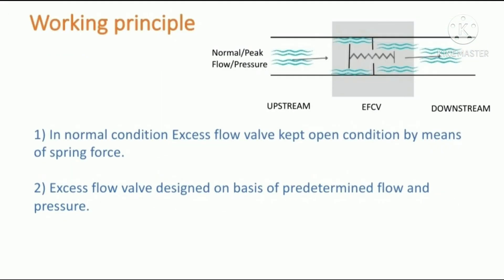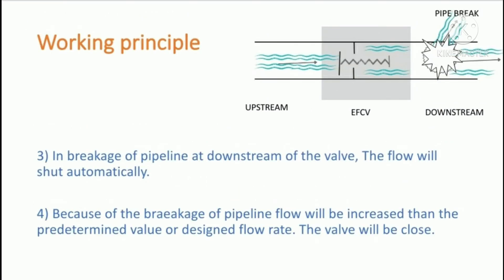Working principle: you can see the sketch of the excess flow valve showing upstream, downstream, and the flow of the fluid. In normal conditions, the valve is kept open by means of spring force. The excess flow valve is designed on the basis of pre-determined flow and pressure.